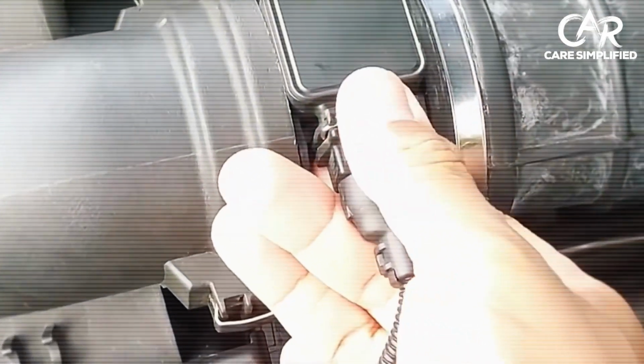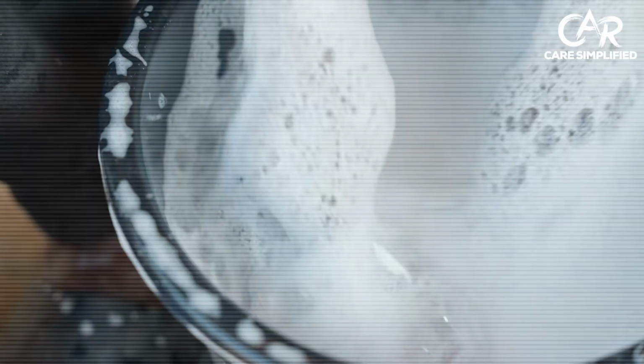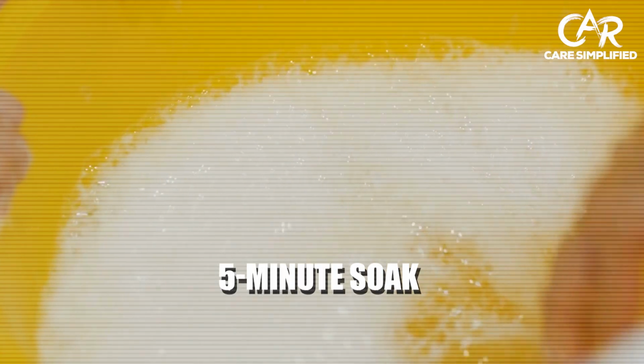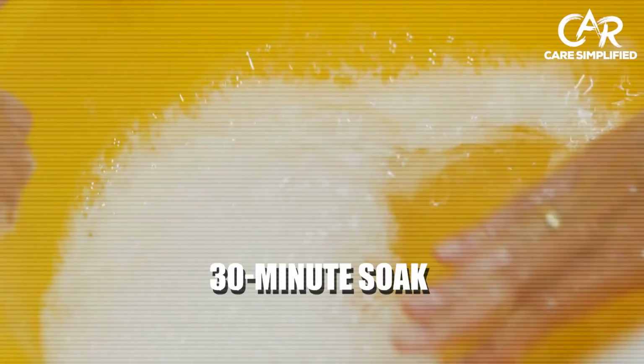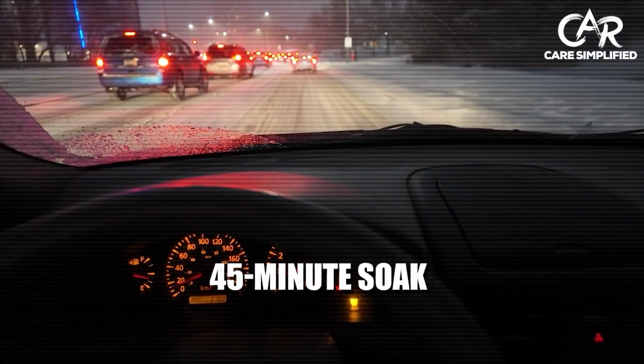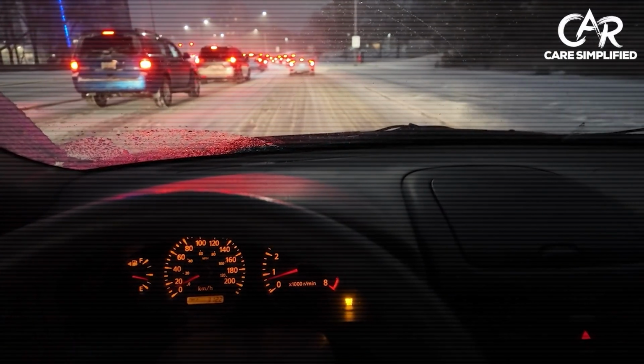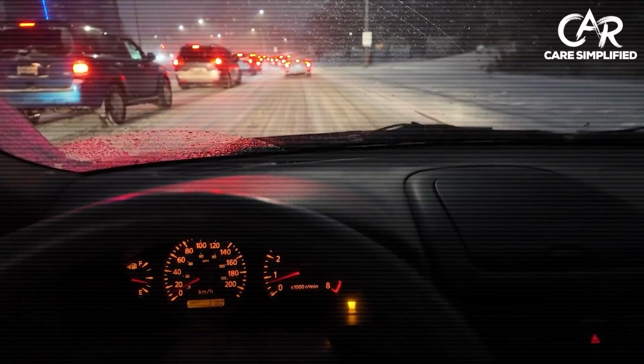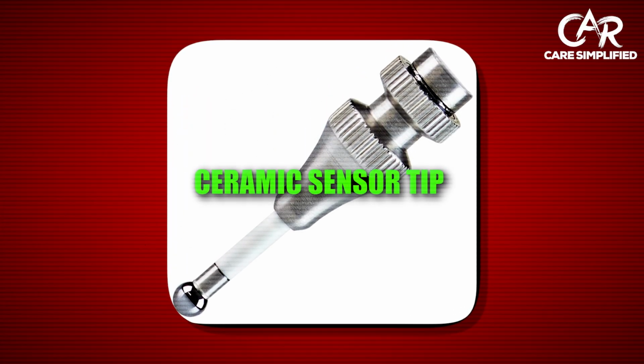Solvents attack this layer chemically but take the platinum with them. The warm soapy water protocol works by hydrating and swelling this bonded layer over time, then releasing it through agitation. Here's the testing data. 5-minute soak gave 40% contamination removal, 30-minute soak gave 95%, 45-minute soak gave 95.3%, diminishing returns after 30 minutes. So, submerge only the ceramic sensor tip in the warm solution.